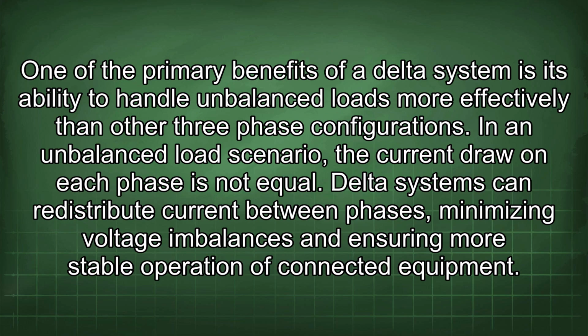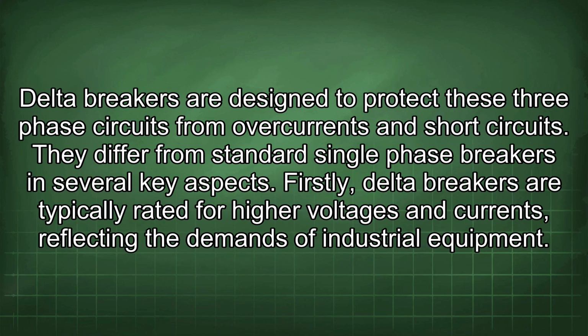One of the primary benefits of a delta system is its ability to handle unbalanced loads more effectively than other three-phase configurations. In an unbalanced load scenario, the current draw on each phase is not equal. Delta systems can redistribute current between phases, minimizing voltage imbalances and ensuring more stable operation of connected equipment. Delta breakers are designed to protect these three-phase circuits from overcurrents and short circuits.